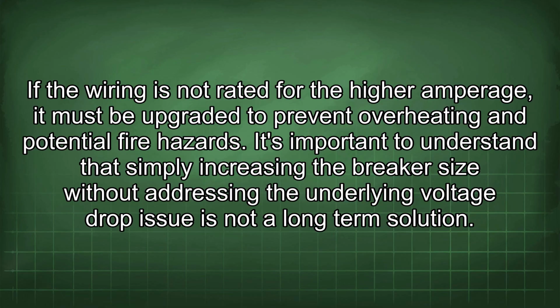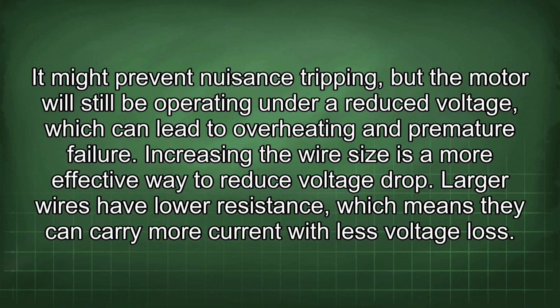hazards. It's important to understand that simply increasing the breaker size without addressing the underlying voltage drop issue is not a long-term solution. It might prevent nuisance tripping, but the motor will still be operating under a reduced voltage, which can lead to overheating and premature failure. Increasing the wire size is a more effective way to reduce voltage drop.